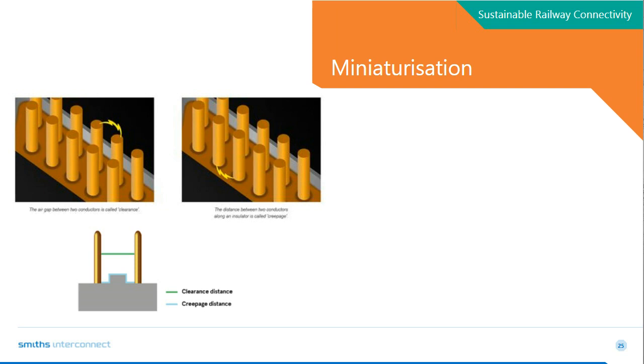Creepage distance prevents degradation due to nominal or continuous voltage. The other one, clearance distance, is the shortest direct distance between two electrical conductors. This is the green line, and the blue line you can see in the picture.